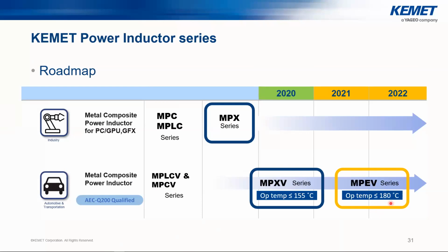Now, if you think, I don't care about your 180 degrees, I still take my 125, please consider the maximum temperature will give you a maximum current which is much higher than the standard item, because your self-heating can be much more than 40K. If your application temperature is around 80 degrees, you can have a self-heating of 100 degrees. So this might be truly interesting.